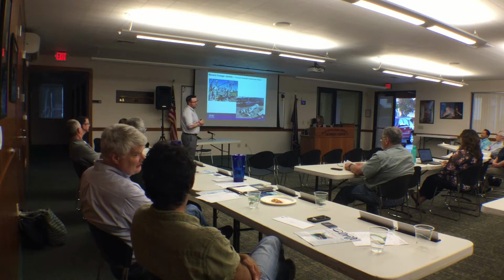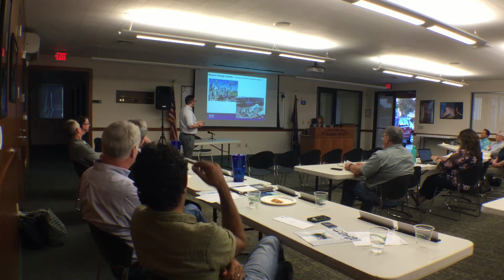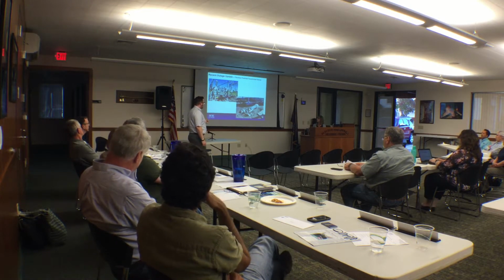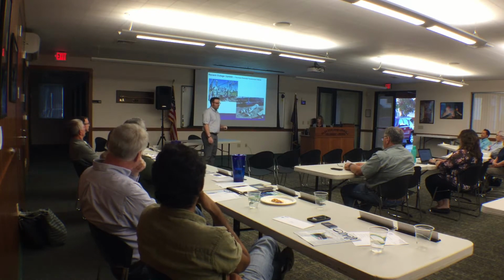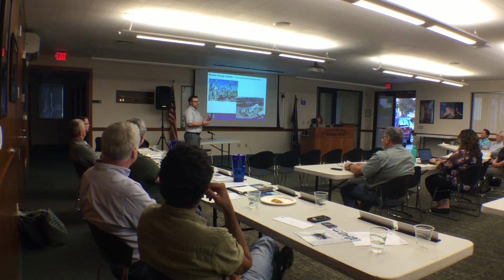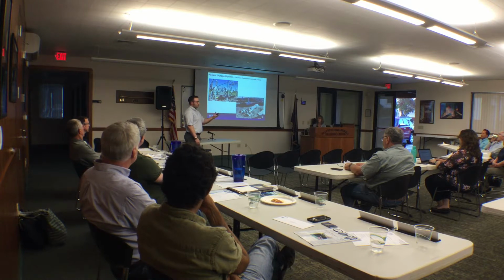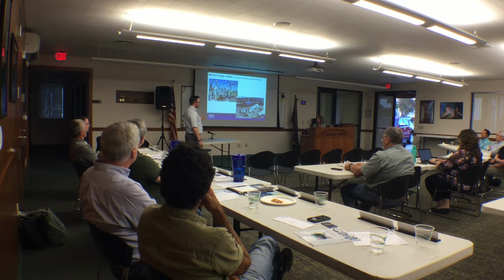Also wanted to update you on a recent event we had at one of our substations, at Thurston Substation. If you were on the feed off of that other line, you wouldn't have seen this, but the upriver folks off of that line in our generation unfortunately suffered an outage from this. This is in Thurston Substation—these devices had a failure on one called a potential transformer.